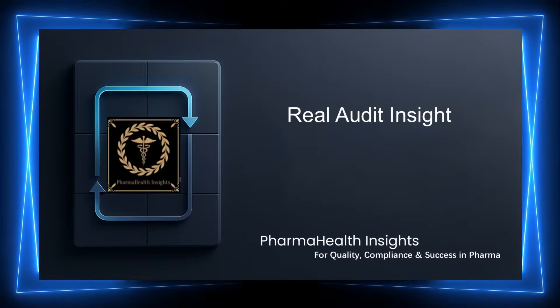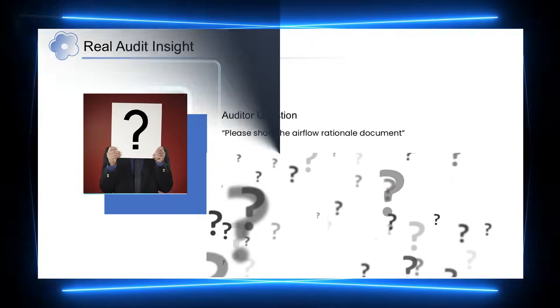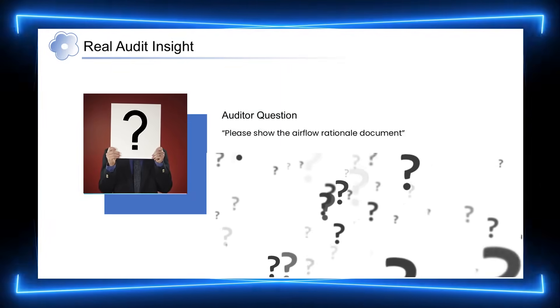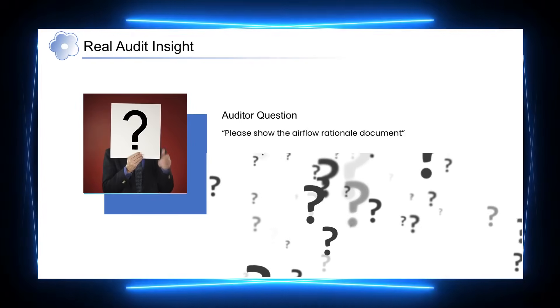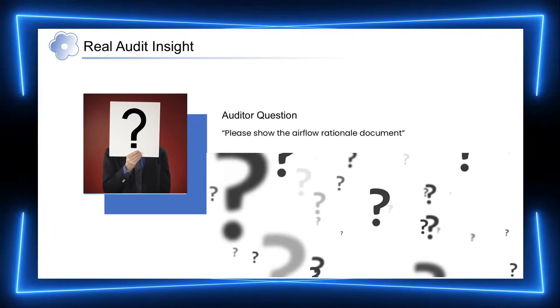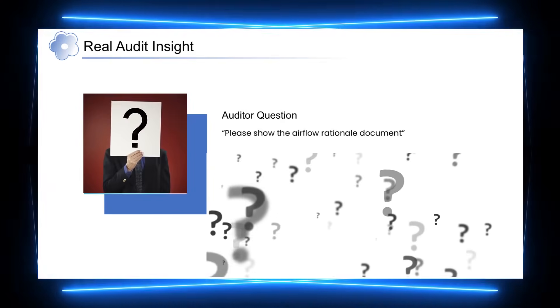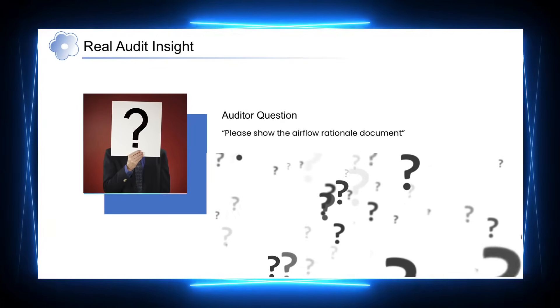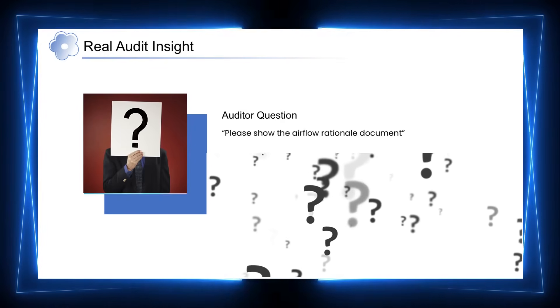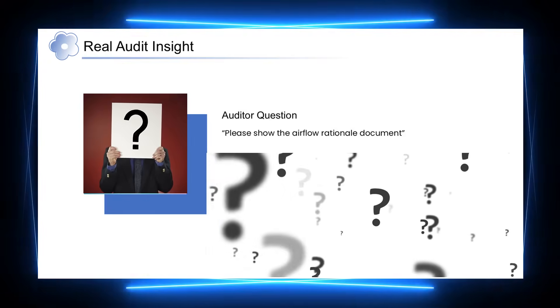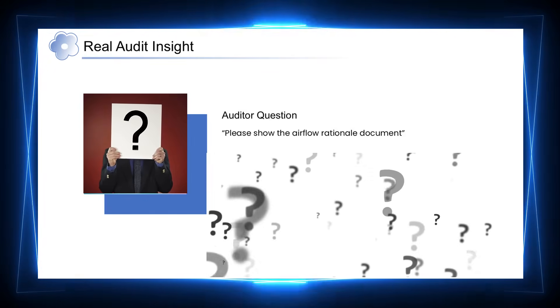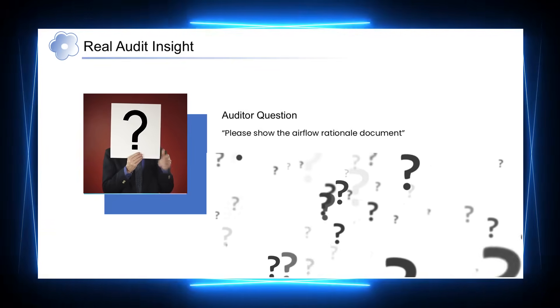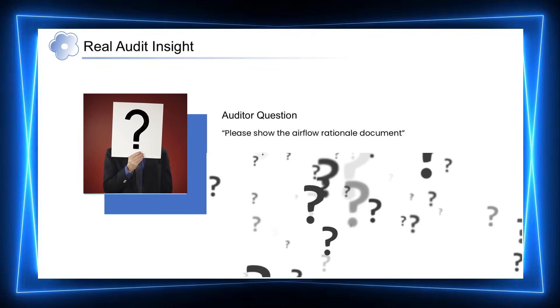Let me share a real audit experience. The system is installed, qualified, and operating smoothly. There are no visible issues in day-to-day operations. Then the auditor asks a simple question: please show me the airflow rationale document. When this document is missing or incomplete, it immediately raises concerns — not because the system is failing, but because the logic behind the design has not been clearly documented. This highlights an important lesson: in GMP, control must not only exist, it must also be clearly explained and justified.